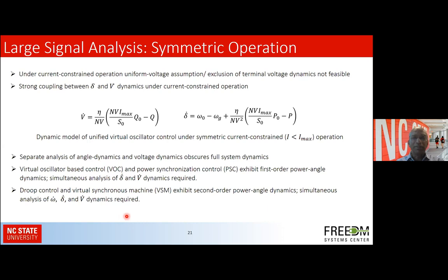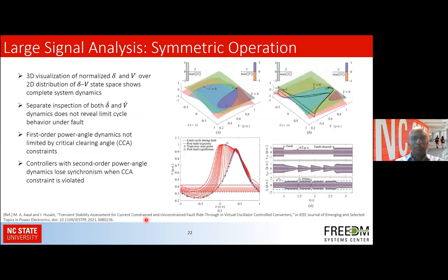So the VOC-based methods and the power synchronization-based methods exhibit first order power angle dynamics, and simultaneously analyze the V delta and the delta angle dynamics, whereas droop and virtual synchronous machines exhibit second order power angle dynamics, which makes it more challenging because the order of the system increases further. I'm showing you an example from our paper on transient stability assessment, noted here at the bottom. Taking into account both the voltage dynamics and the current dynamics in this left figure, prior to the fault there are two intersections, and one of them is a stable operating point and the other is unstable.